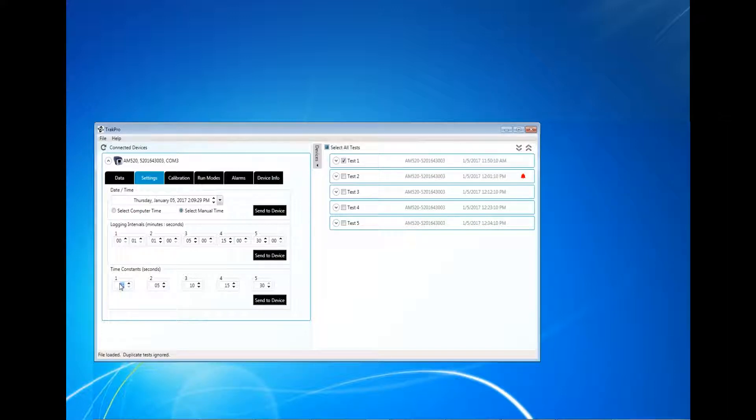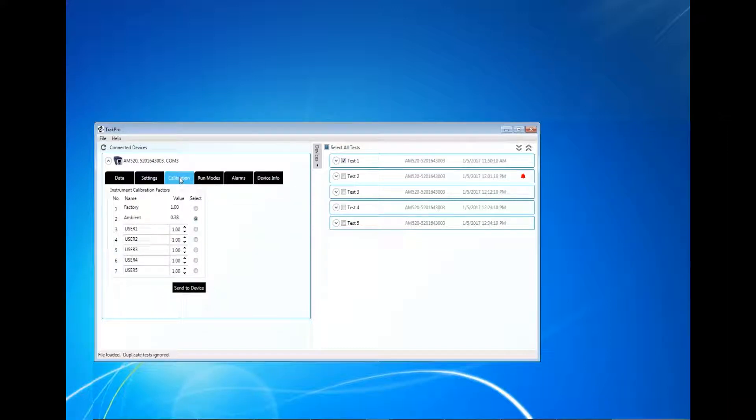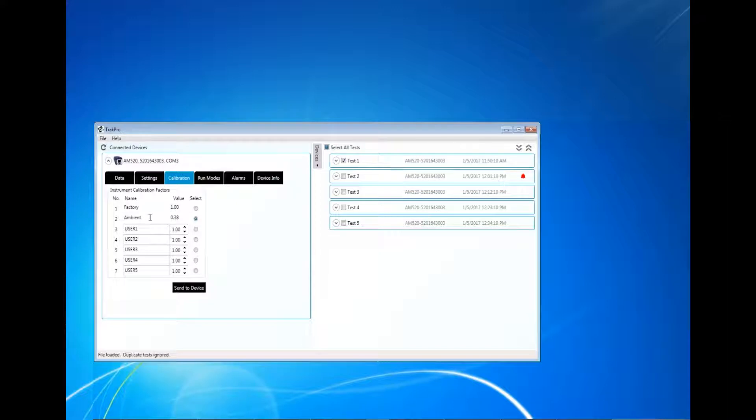The calibration tab allows the user to configure the instrument's calibration factors. The AM520 user guide refers to the calibration factors as user CALS. User CALS 1 and 2 cannot be changed and are preset at the factory.